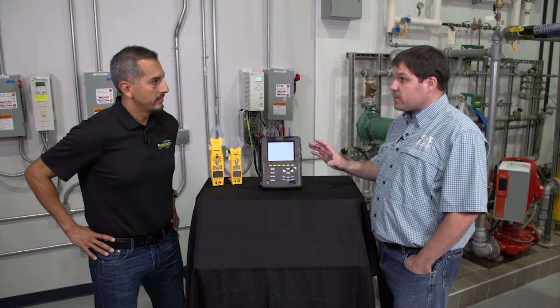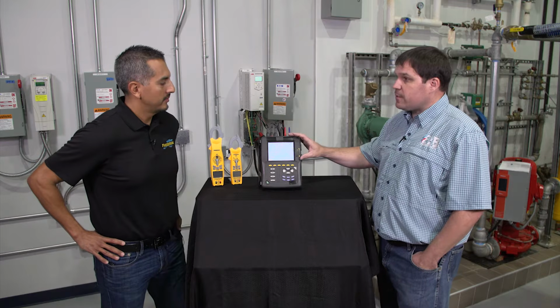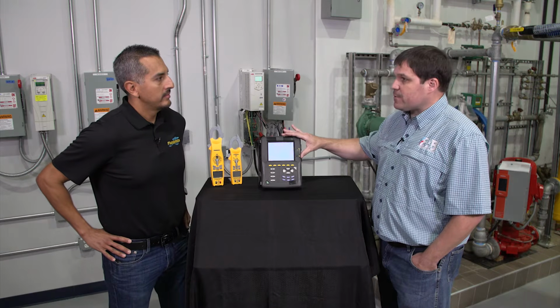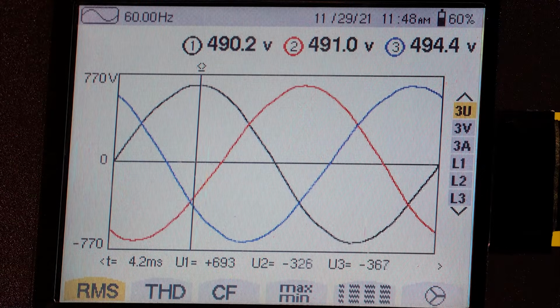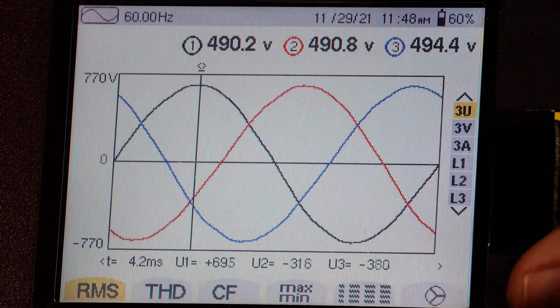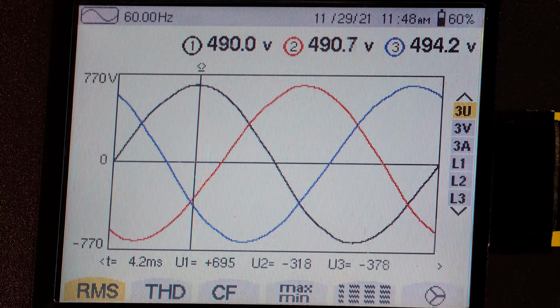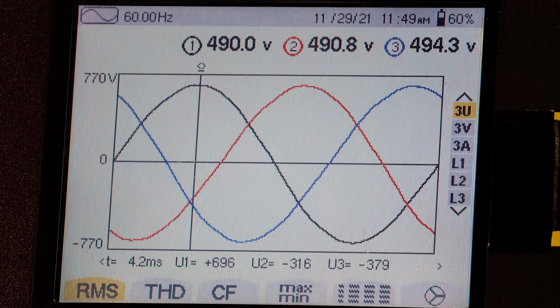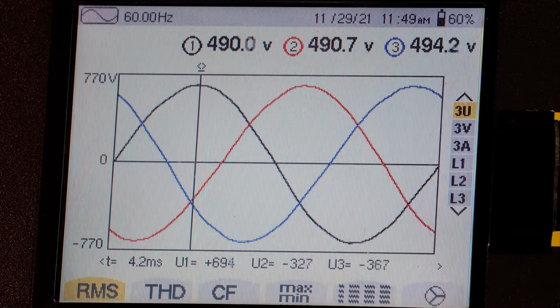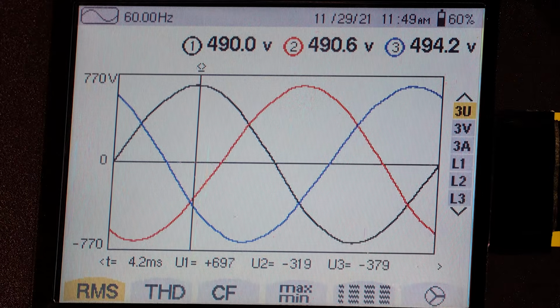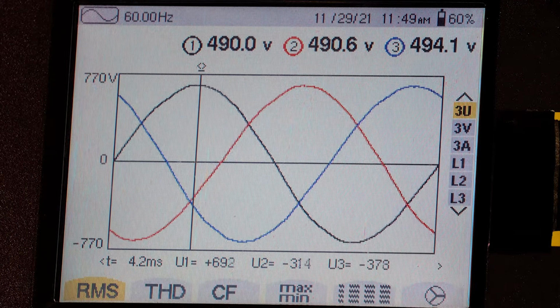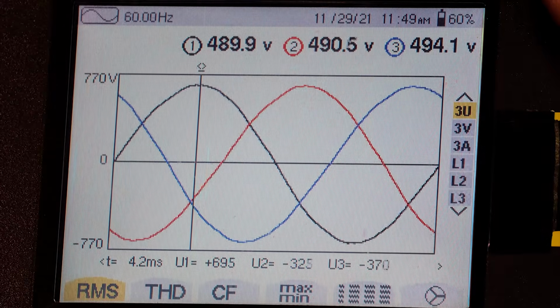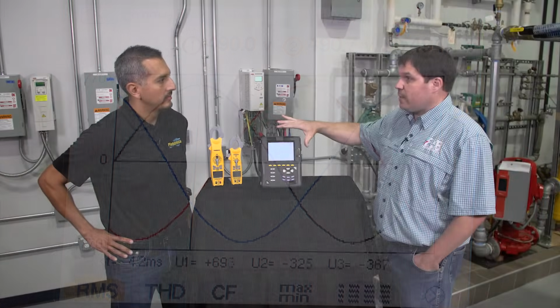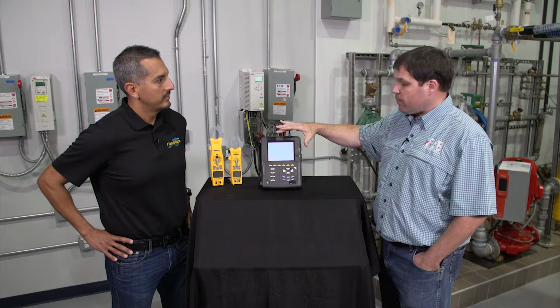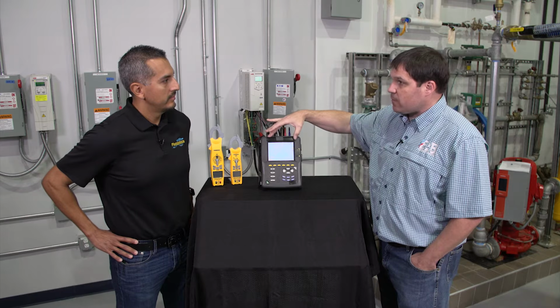Well, Tony, that's a great question. To answer that, we first need to talk about what a power signal looks like as it enters a VFD before it's processed. Here on our scope, we have what's considered a pure sine wave, or what you'd receive from the utility. This is 60 hertz power, with each of 3 phases 120 degrees out of phase. You can see they're perfectly shaped. Any meter rated for measuring 480 volts could measure this type of signal.